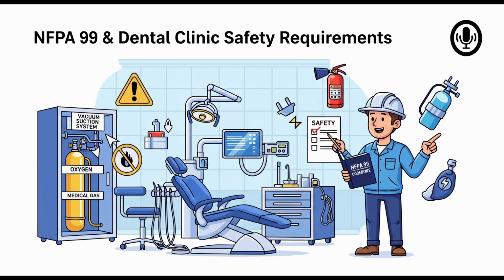Chapter 4. It defines 4 categories. Category 1 is the highest risk system. Failure is likely to cause serious injury or death. Think major surgery, life support. Category 2 is where failure is likely to cause minor injury. Category 3, and this is where dental often lands, is where failure is not likely to cause serious injury or death. And Category 4 is the lowest risk, where failure has minimal impact on patient care. So you figure out the risk category of the procedures first. Exactly. You determine the risk, then you apply the requirements for that specific category. The code doesn't care so much if it's a hospital wing or a standalone clinic. It cares about the risk level of what's being supported.